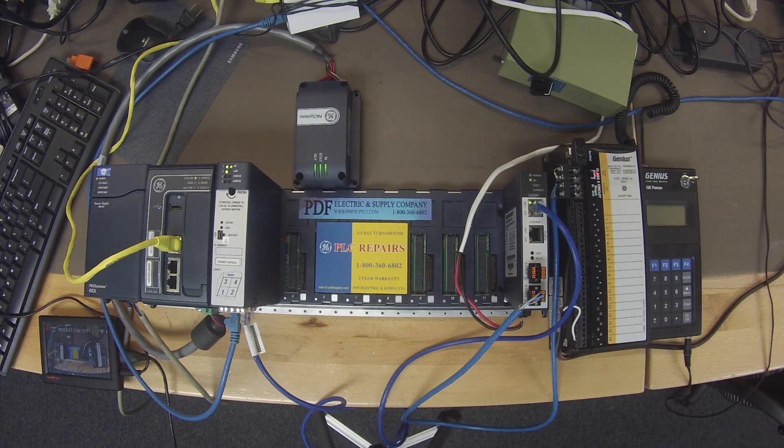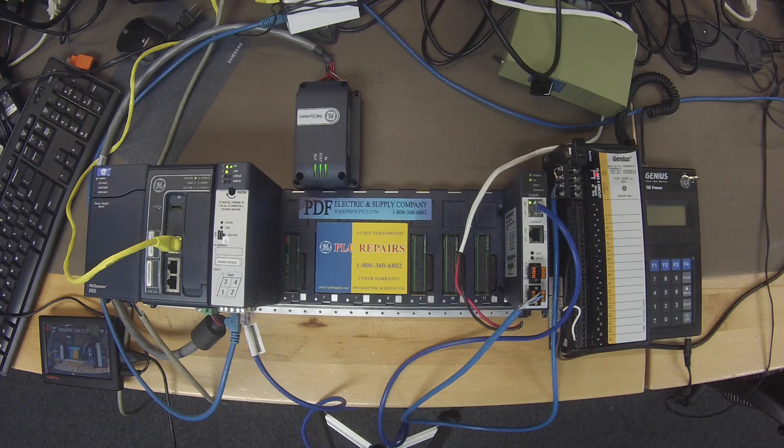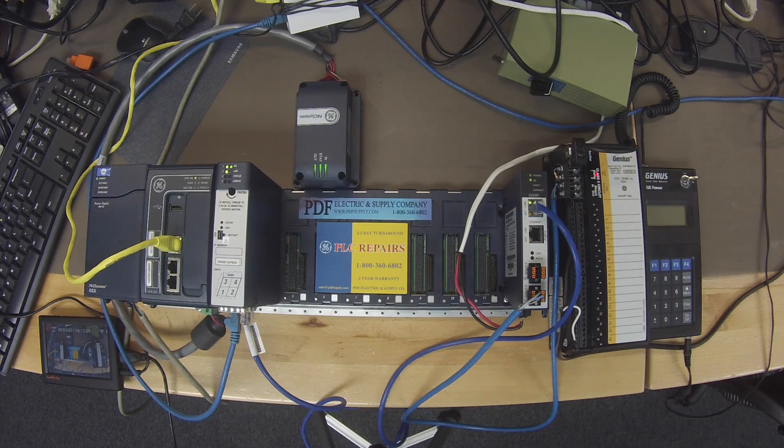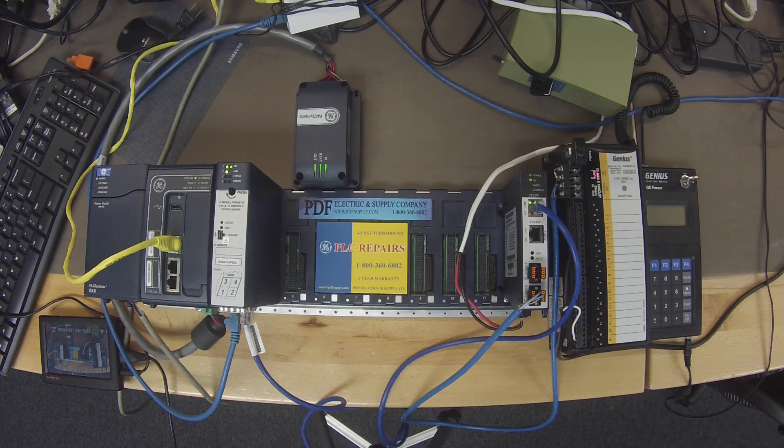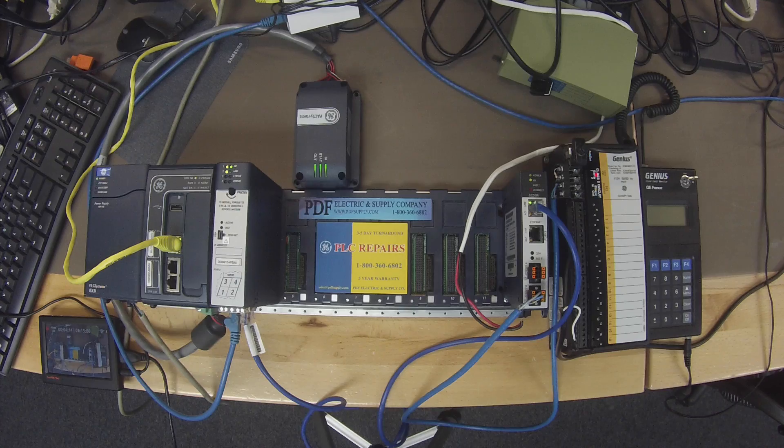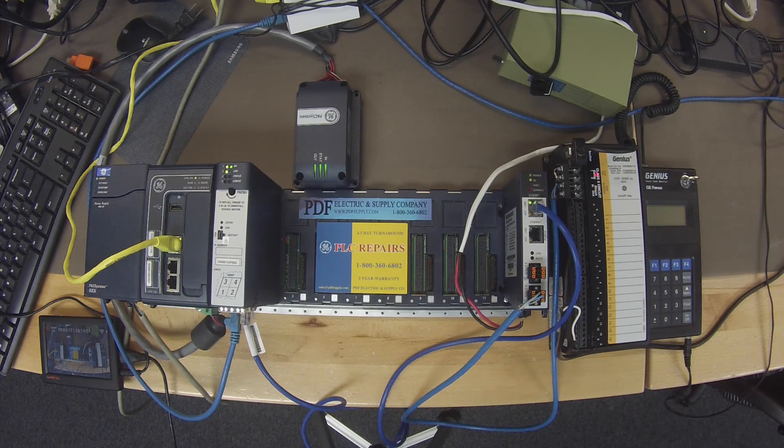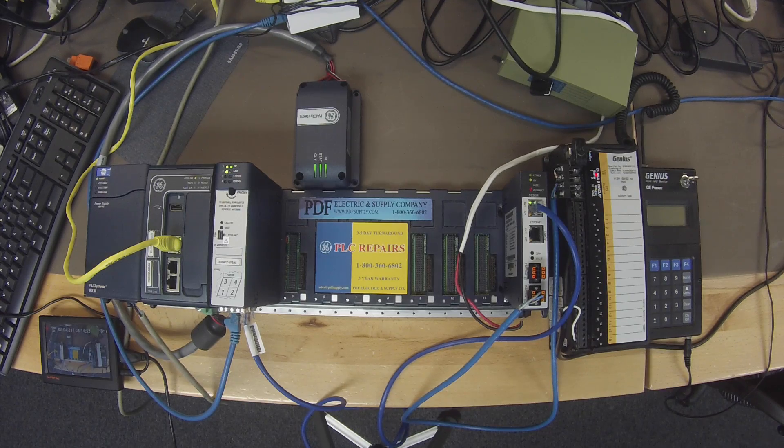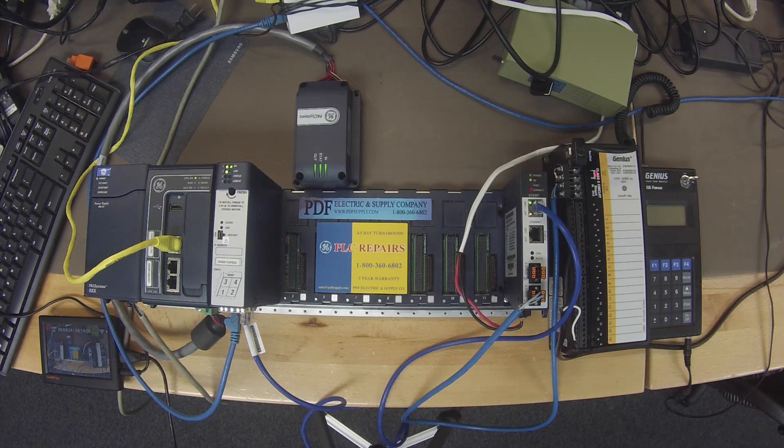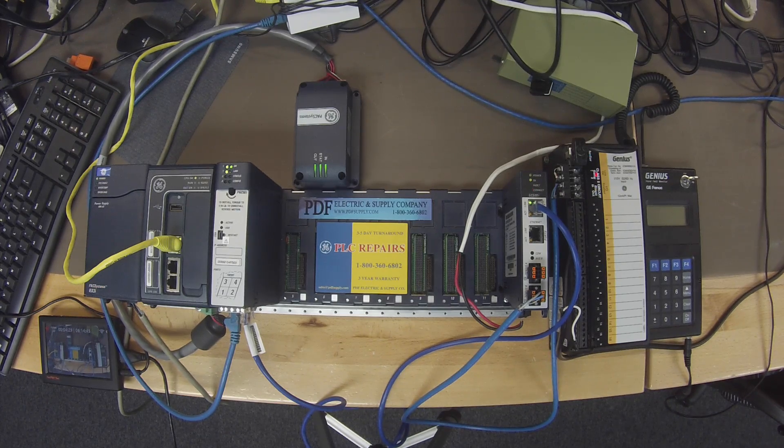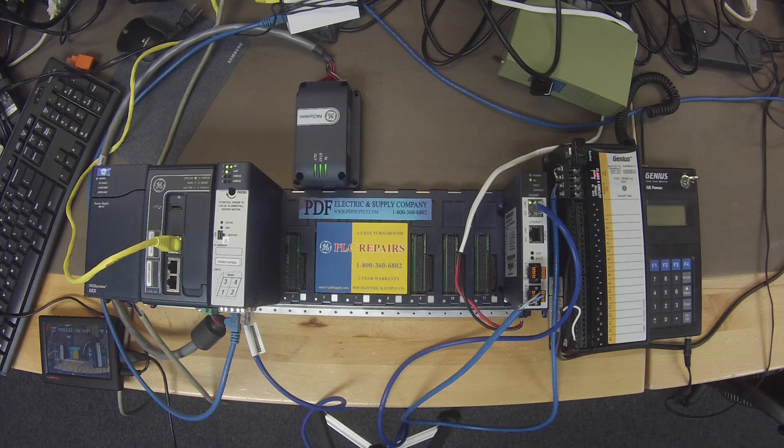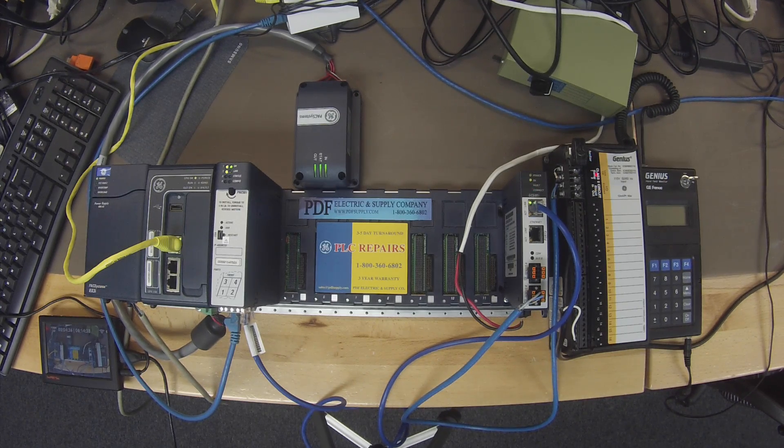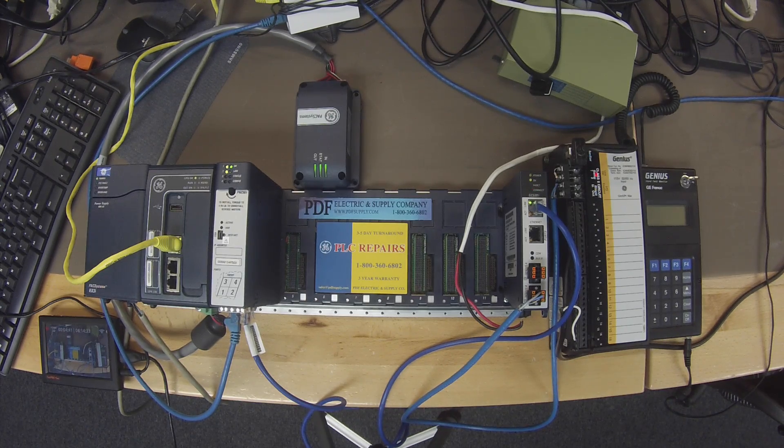Another thing that you're going to need to do, and I'll briefly touch on this later, is that prior to actually establishing this GCG, you need to get what's called a General Station Description Markup Language. This is the communication between the Profinet and the Genius Communications Gateway. That's called a GSDML file. You can get this GSDML file by going to your GE Intelligent Platforms webpage under Support. You go to Support Home, and under Search, you just simply type in the letters GSDML. And you need to download the file that goes along with that.